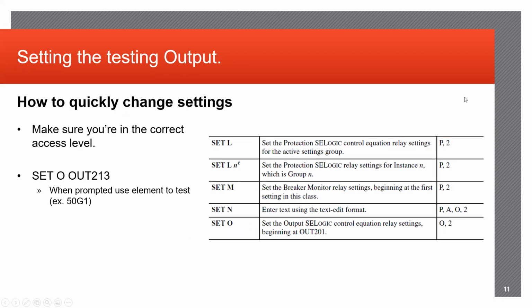Going back again, the relay terminal is extremely helpful for setting your outputs when testing. Like I said before, if you hook up a spare output to your test set, you can manipulate that output as many times as you want during the course of testing without having to log into the relay and change it directly and send new settings back and forth, because that would take forever. This way in the terminal screen, you can just change it, press enter, and the relay just takes it, and you can go on with your testing and then change it again on the next test. It's pretty convenient and super helpful for getting testing done time efficiently.